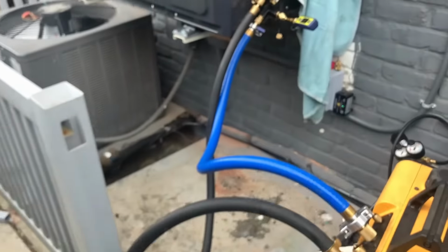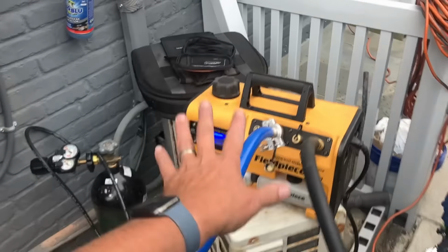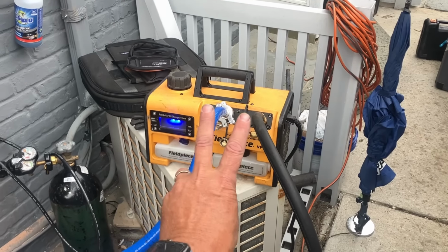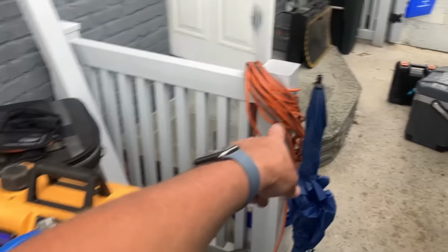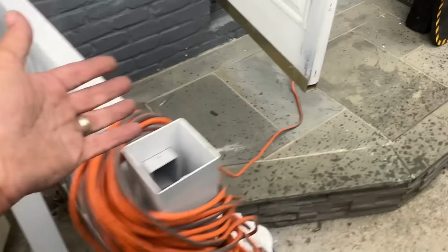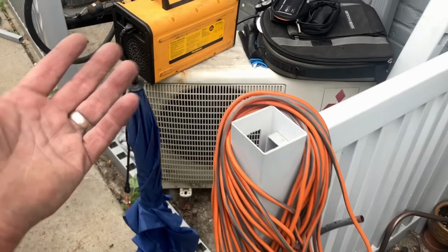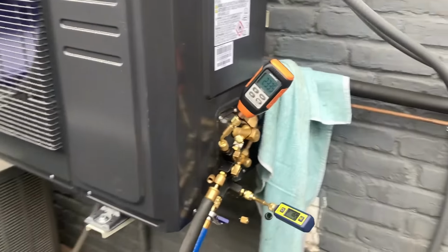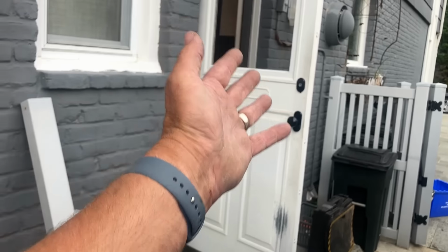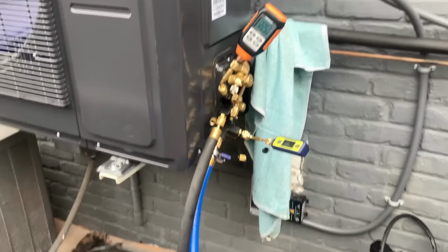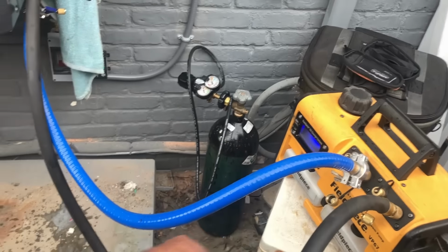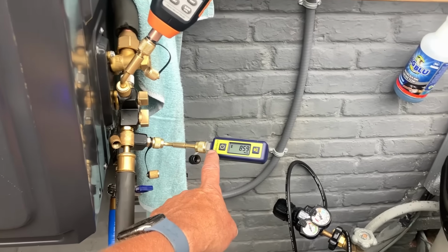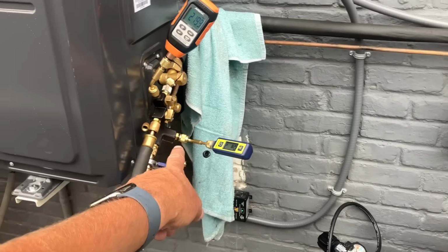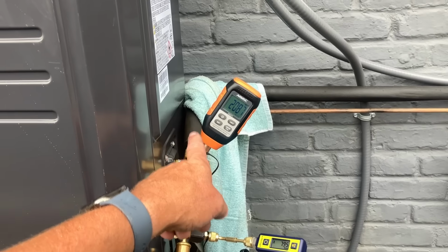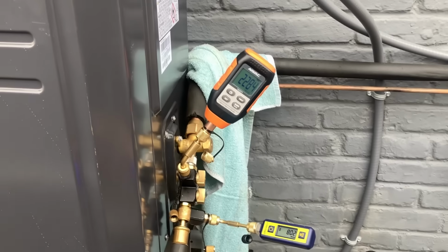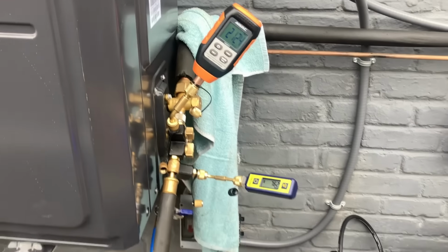All right folks, it's 10 minutes after 2 o'clock here. I have my Field Piece VP67 6CFM 2-stage vacuum pump set up. Got a 100-foot extension cord, ran it right to the kitchen. My 25-foot extension cord I left at a job to power a water booster pump and never went back, so I'm a schmuck for forgetting it, and now I'm using a 100-foot cord when I only need a 20-foot one. I'm using the Appion hose here and the ACiQ Tools hose there. I've got the Blue Vac Plus micron gauge on my 3/8 line, and I have the NAVAC, which I don't trust, on the 3/4 inch line - I don't trust it because when I close it off, it spazzes out anyway.